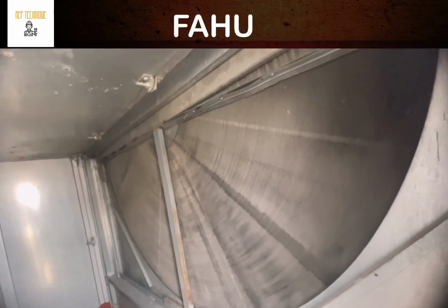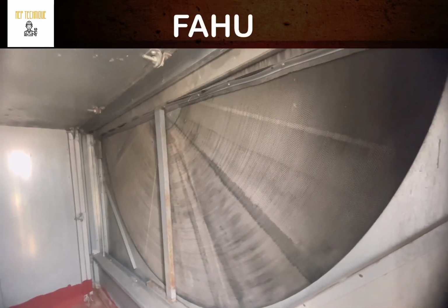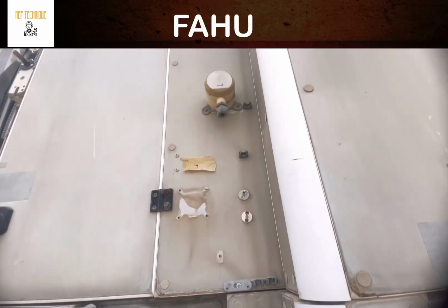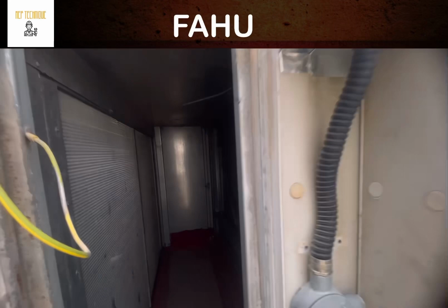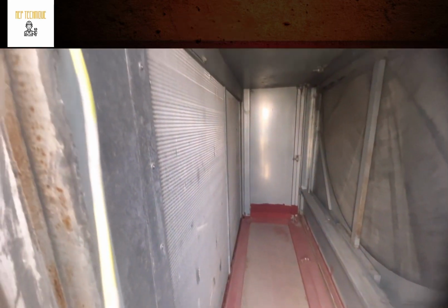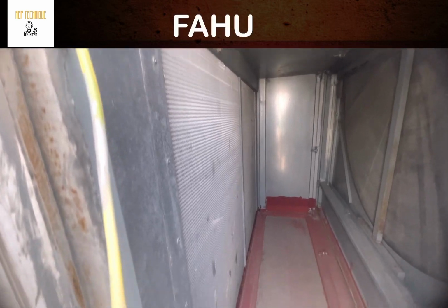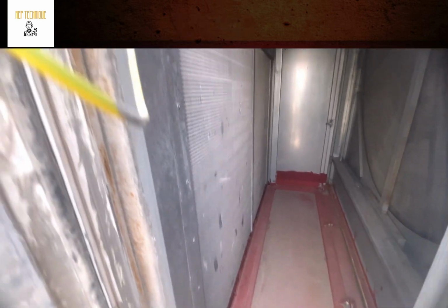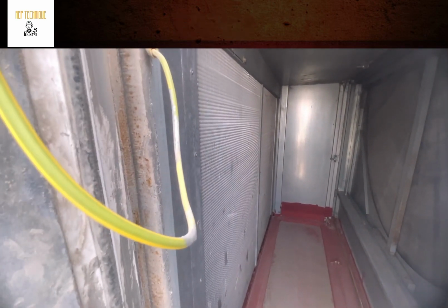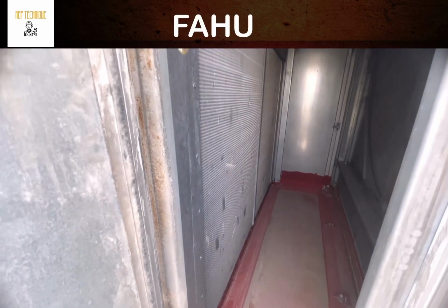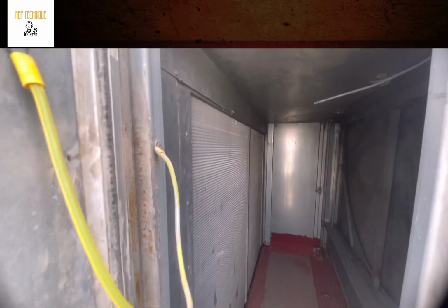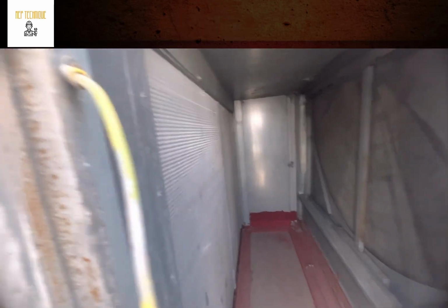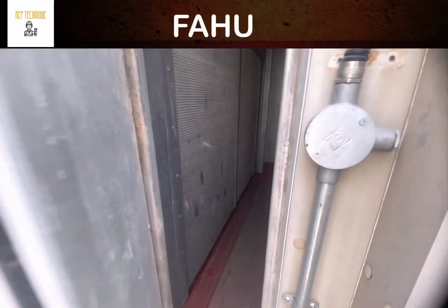Half of the heat recovery wheel is in the fresh air section, and half of the wheel is in the exhaust system. You can see only half of the section here. Then after that, this is the coil section, where the chilled water is connected. It is made with copper coil, and the copper coil is what handles the chilled water.